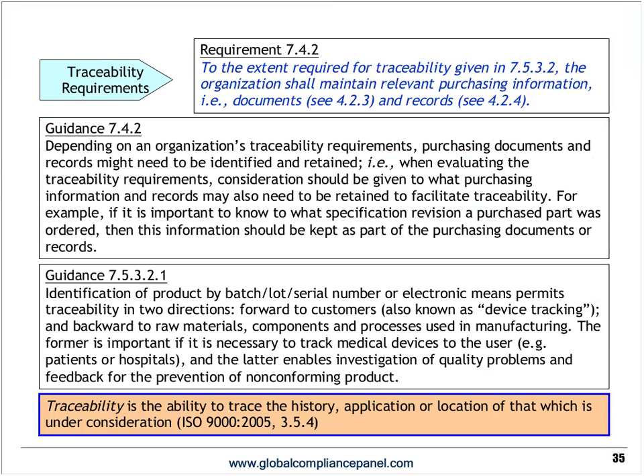Traceability. So traceability shows up as one of these things that's in 13485. That's not in ISO 9001. So you have to maintain relevant purchasing information, for example, documents and records. And the purchasing documents may need to identify the traceability requirements, particularly if you need to make sure that you know the specification revision of the part that you've ordered. This information is going to be in the purchasing documents or records.